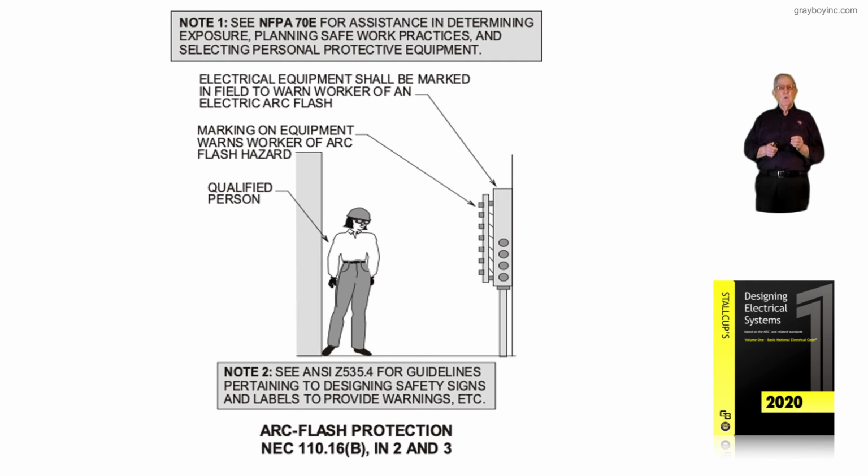Now, it depends on which one you're calculating. NFPA 70E 130.5 requires the top portion, 1 through 4, to be calculated, or we would look at the task we're performing in the equipment, for example, in some cases, and we would use the tables based upon the task in NFPA 70E. So all we're pointing out here is that there is a calculation required for safety for the electrical worker working on this equipment with covers off with it energized.